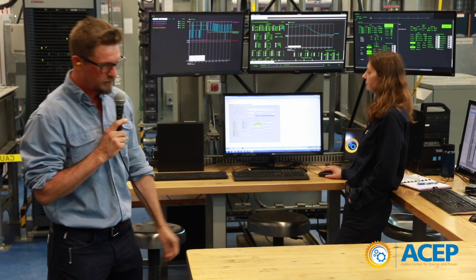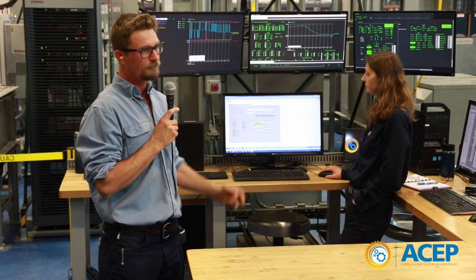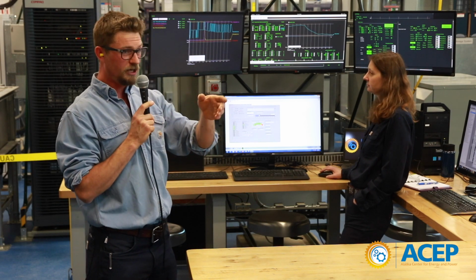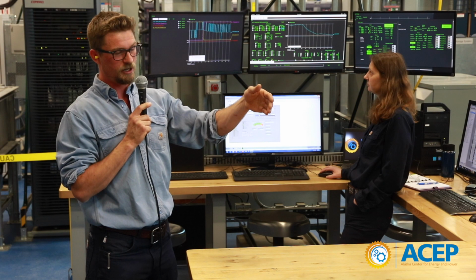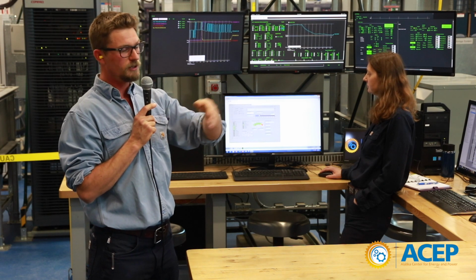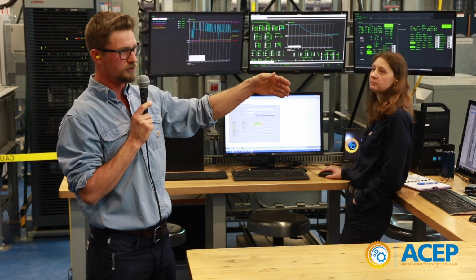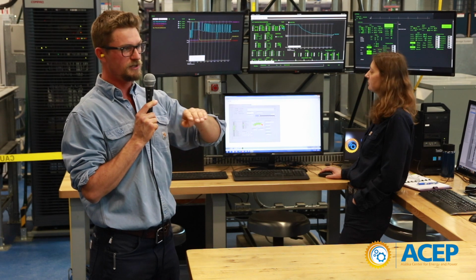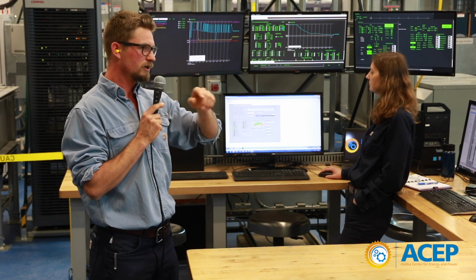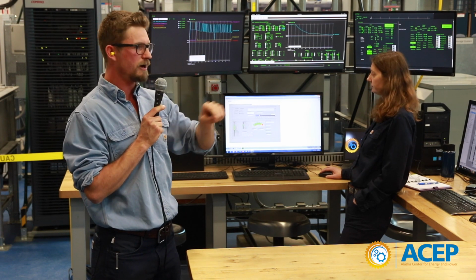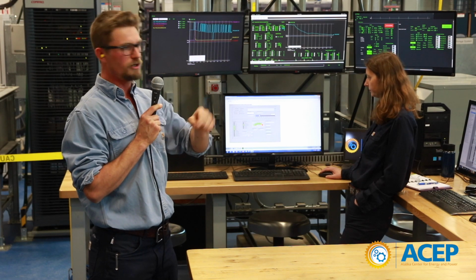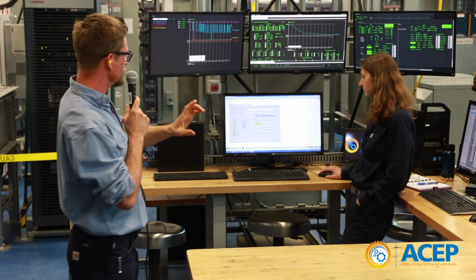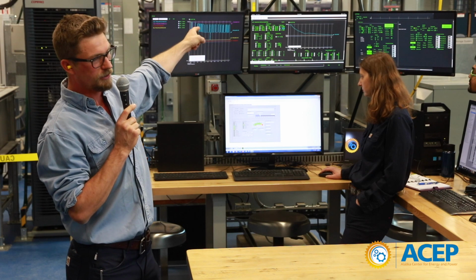One difference between the inverter and the generator: remember, with the generator you couldn't get close to putting zero load on it, or let the wind power get close to supplying all the load, because then you're in the danger zone — getting close to reverse powering your generator. You also didn't want too low a load on the generator. Our inverter doesn't care about that.